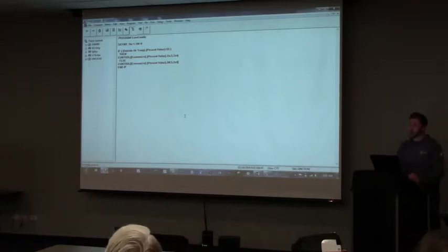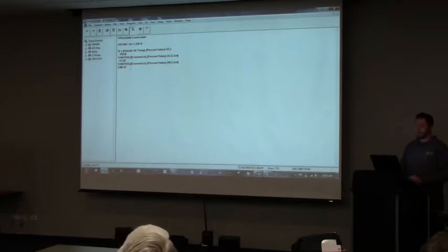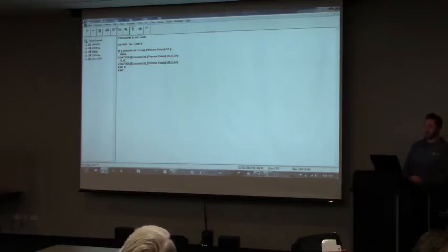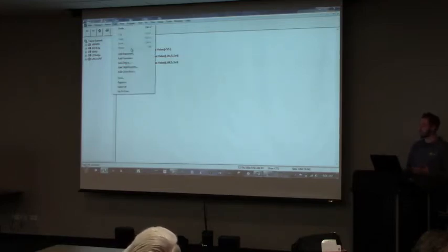Essentially the code's pretty much written, but at the end of a program you have to put end, otherwise your program will not compile right. So we have the end if now, so now I just got to write end. So now the program's completely done, we want to compile it, and there you go. So now I have an econ enable disable program right there. I know it doesn't have a deadband in or anything, but it's just kind of nice when you use Edit, because it leaves you fewer errors of actually writing the code through CPL.